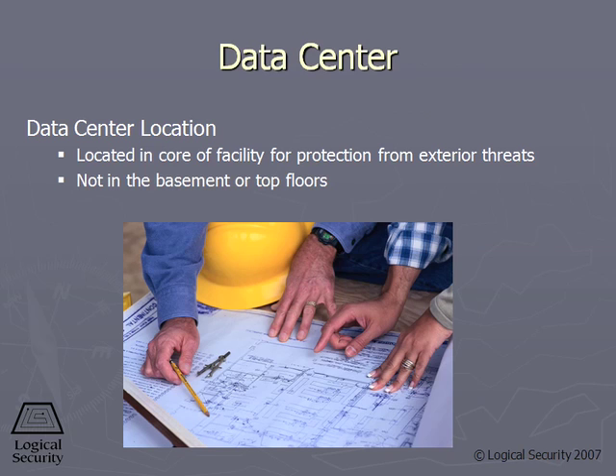Next, we'll take a look at where we should locate the data center. The data center, of course, is one of the more valuable areas in our corporate environment. So we'll want to protect this from these exterior threats. I never want to put the data center on the lower floors because these are more subject to flooding, and I generally don't want to put them on the higher floors because if the building ever catches on fire, fire always rises, and also too close to the roof, roofs very often will leak. You want to keep your data center towards the center of the building, usually away from exterior walls.